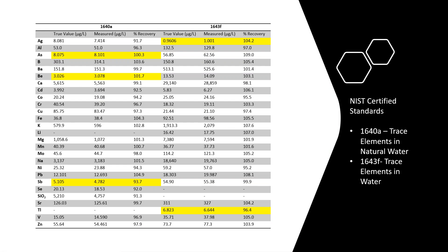Now, we also ran some samples that were digested. And these are NIST-certified standards that we ran, 1640A, 1643F there. And the recoveries that we're able to get on these NIST standards were all within 10 percent. So, everything came back really good. We're able to get really good recoveries on these. The highlighted elements that you see here, those were ones where we actually were able to get really good recoveries despite having a fairly low certified value based on our calibration curve. And we're still able to get excellent recoveries.